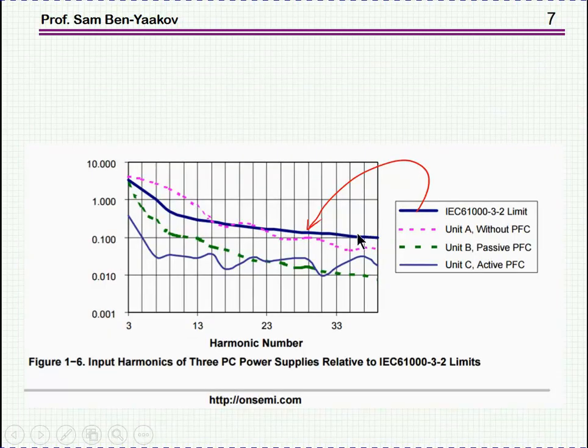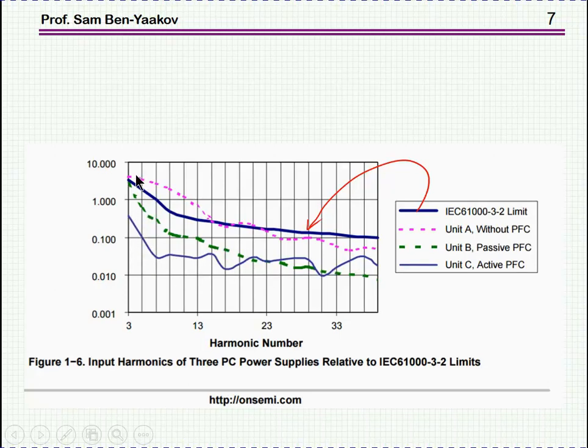Class D is also defined differently — as milliamps per watt. So for a 100-watt piece of equipment, it will be about 300 milliamps for the third harmonic. The absolute limit is 2.3 A, so even if power is very high, you cannot go above this value, which is actually the class A limit. This curve shows the limits on a logarithmic scale. The third harmonic is 2.3 A, and the limits go down for higher harmonics. Different pieces of equipment are shown as examples — most are within limits, but one is outside and will not pass the standard.